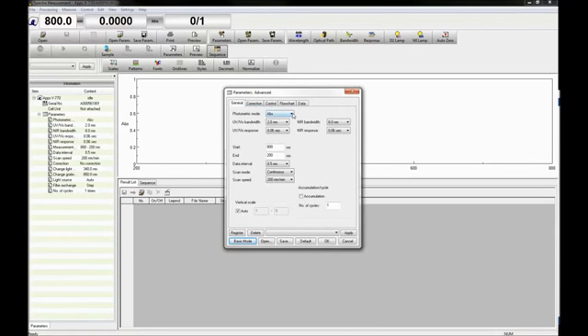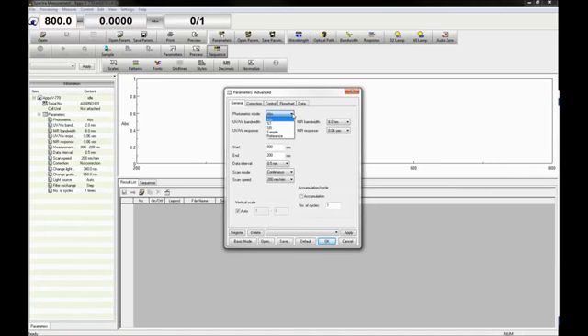Here you can specify which photometric modes to measure: absorbance, transmittance, reflectance, sample single beam, or reference single beam.